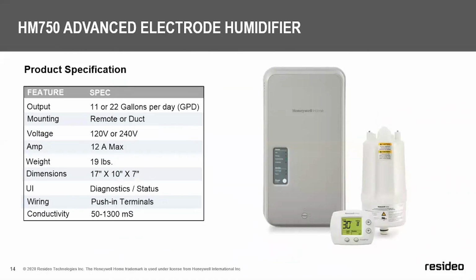The basic specifications of the HM750 are shown here. This humidifier provides 11 gallons per day or 22 gallons per day, depending on whether you are wiring to 120 volt or 240 volt applications, with a maximum amp draw of 12 amps. This can be mounted via remote or duct mount. And here I stand corrected, it is actually a 19-pound dry weight. I was remembering 18, not bad for an old guy like me.